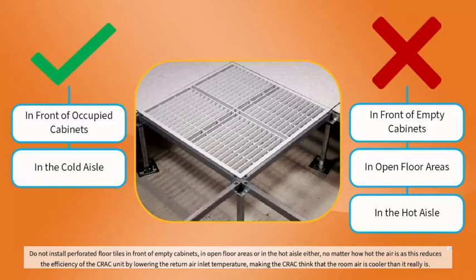Placing tiles in the hot aisle reduces the efficiency of the CRAC unit by lowering the return air inlet temperature, making the CRAC think that the room air is cooler than it really is.